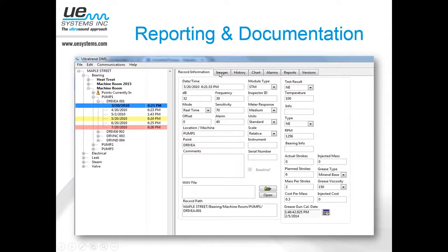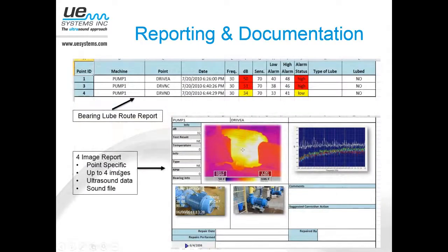We can also put images in and look at trend charts, so there's all kinds of different reports we can generate. Here you can see it's what we call a 4-image report. Here we actually imported an infrared image of that bearing as further documentation, and here's a digital photograph to document. So if you attach this to a work order, the person knows exactly where to go out and make the repairs.